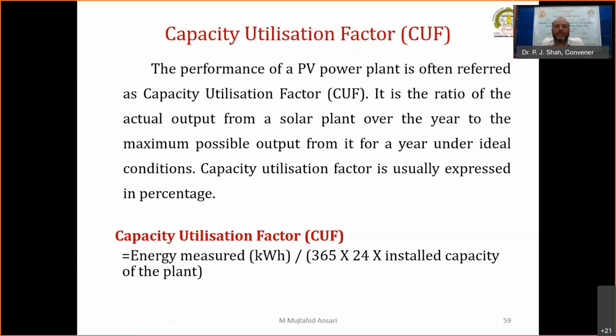We cannot analyze the plant very accurately only by the capacity utilization factor, because it does not consider the dust and dirt accumulated on the PV modules. It does not consider the climate conditions, that is the temperature variation and geographical conditions, damage to some of the PV modules, or the down period of MSEDCL. Our on-grid power plant runs only when the grid supply is there. If the grid supply is off, our power generation again becomes zero. Such factors are not included in the CUF, so CUF alone does not show the proper performance of our solar plant.